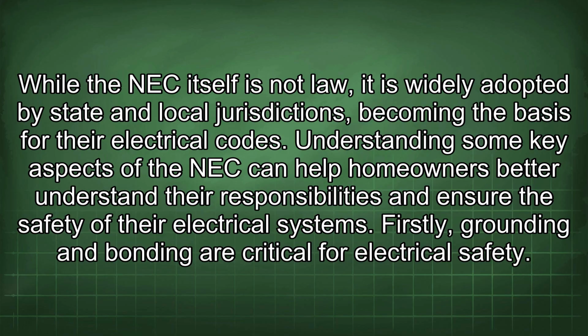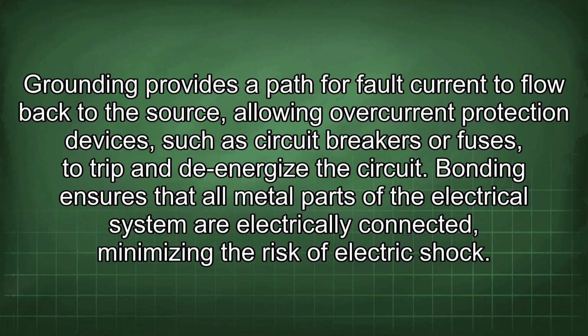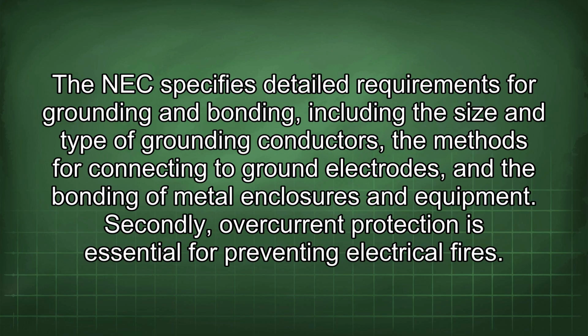Firstly, grounding and bonding are critical for electrical safety. Grounding provides a path for fault current to flow back to the source, allowing overcurrent protection devices such as circuit breakers or fuses to trip and de-energize the circuit. Bonding ensures that all metal parts of the electrical system are electrically connected, minimizing the risk of electric shock. The NEC specifies detailed requirements for grounding and bonding, including the size and type of grounding conductors, the methods for connecting to ground electrodes, and the bonding of metal enclosures and equipment.